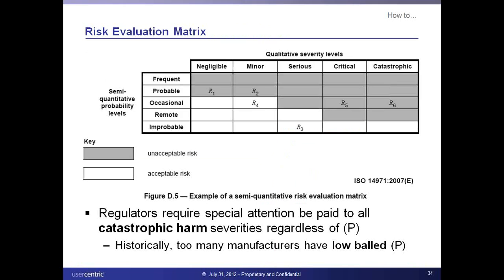Following the prioritization of risk, there is a risk evaluation matrix. Here is one in the same ISO standard, and what you want to recognize is that regulators pay special attention to catastrophic harm, almost regardless of probability. The reason is that manufacturers can lowball the likelihood of risk. So even though you may have a remote or improbable chance, it is something that will be highly scrutinized by regulatory agencies. It's not something that can be overlooked. You need to explain and justify what control measures you put in to handle this. So ultimately, you've got a risk prioritization—take a look at risk evaluation matrices such as this to think about how you want to mitigate risk, and also recognize where the microscope will be focused.